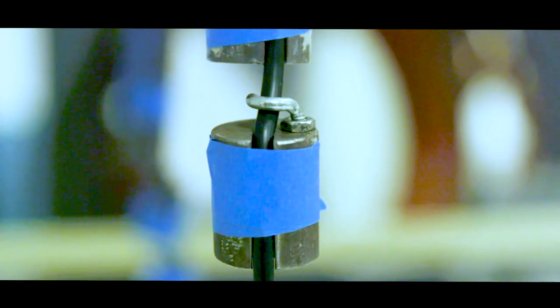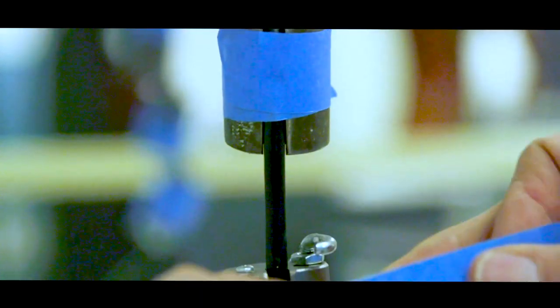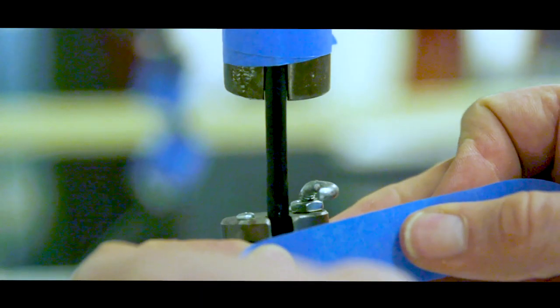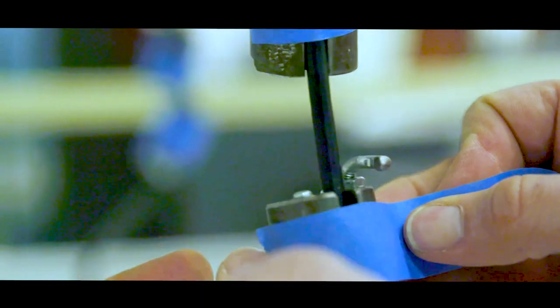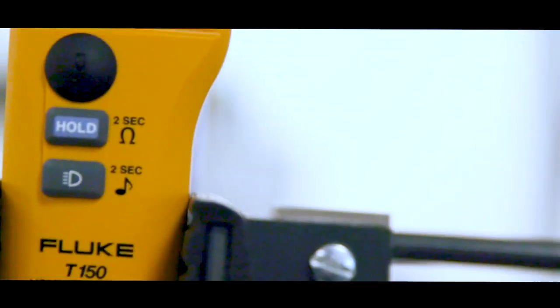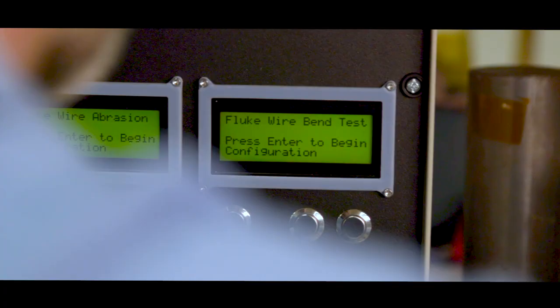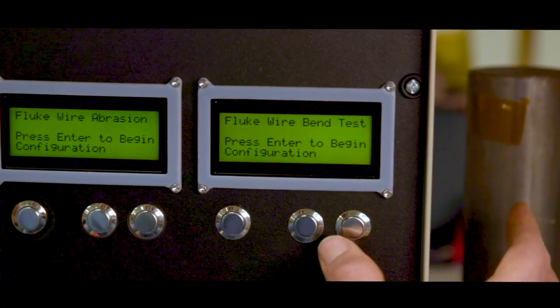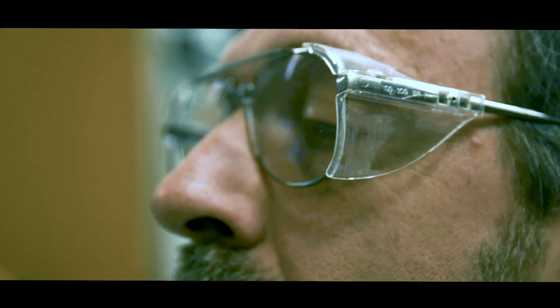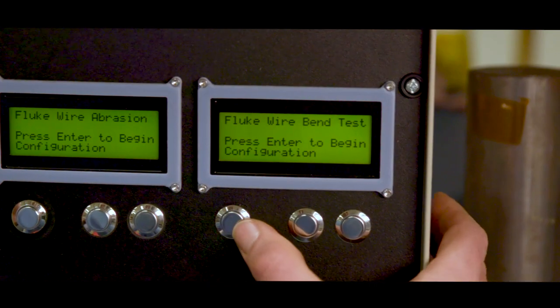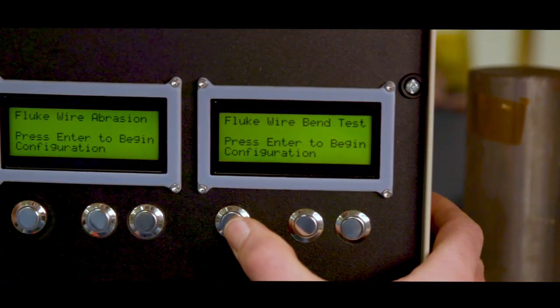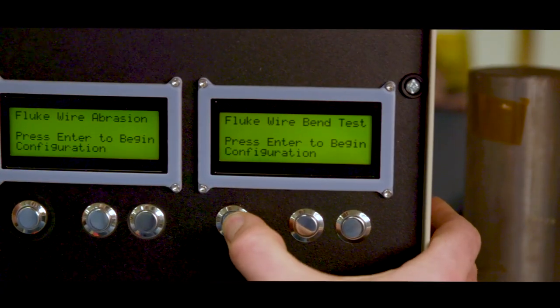Every two-pole tester on the market has to meet certain testing requirements as described in the IEC 61243-3 standard. The IEC standard for test tools specifies that the cable be bent to 45 degrees and 5,000 bend cycles in each direction.